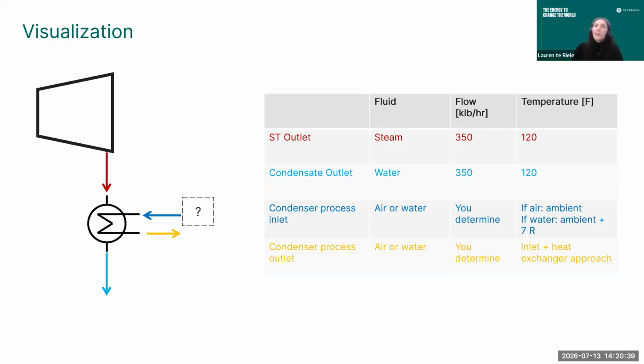I don't know if that happens at large scale in power generation, but it definitely happens at smaller scale. What we do is apply velocity limits - what is a reasonable velocity limit? That's typically closely tied to the pressure drop it induces. If I have a very coily heat exchanger and my velocity is too high, the pressure drop is going to be too high, which drives up the system pressure, which can lead to leaks. So that's something we have to consider.